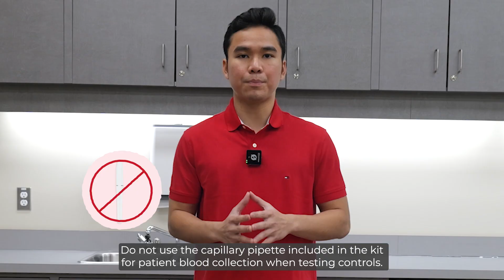This section reviews the complete procedure for testing INSTI controls. This procedure differs slightly from patient testing, so it is important to follow the specific requirements. First, prepare the testing area and gather materials. Use 1 INSTI test kit for each control, a calibrated 50 microliter precision pipette, and control materials at room temperature. Do not use the capillary pipette included in the kit for patient blood collection when testing controls.